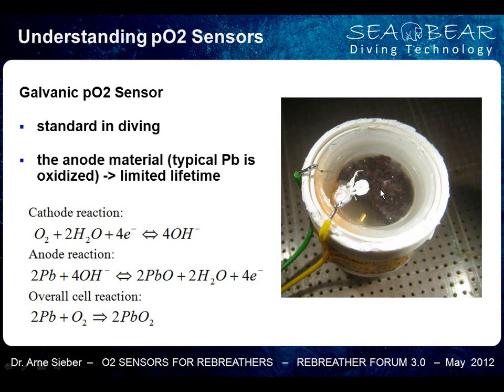So here you have a sensor cell which is open from the back. The board for temperature compensation is removed so that you can see inside. And what you see here, this brownish stuff, is the lead anode. This anode is oxidized over time. For each molecule of oxygen, we end up with 2 oxidized molecules of lead. And what we actually measure in the end are these 4 electrons. These 4 electrons are the sensor current, and we drive this current over a resistor, which in the end gives us a millivolt reading.